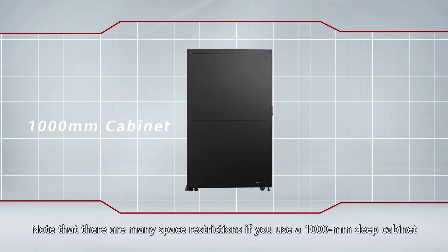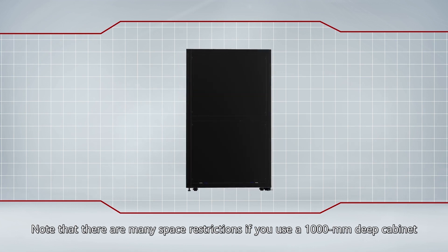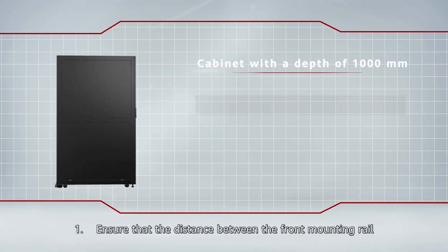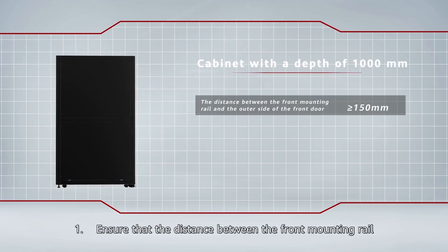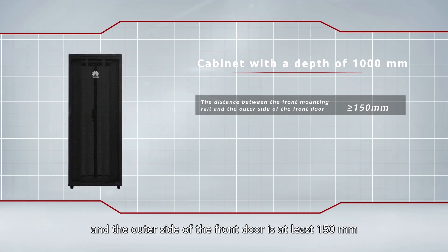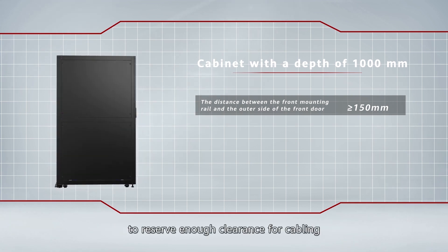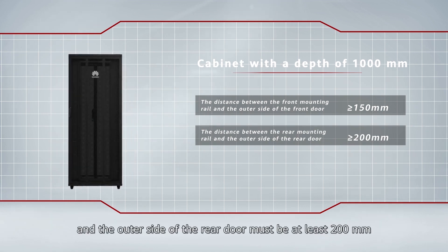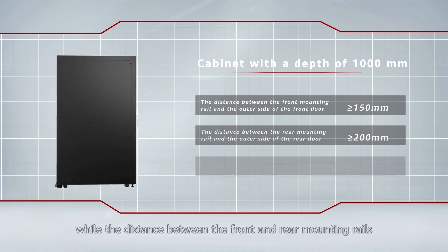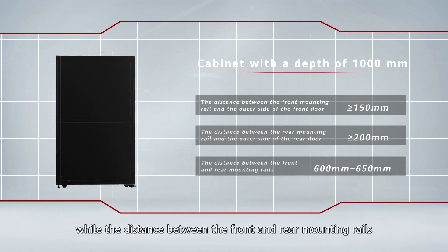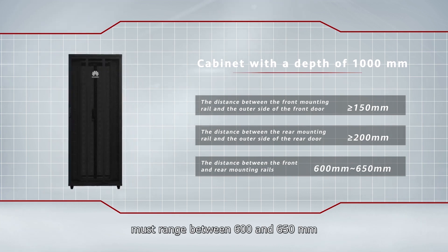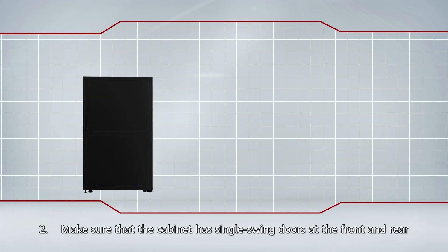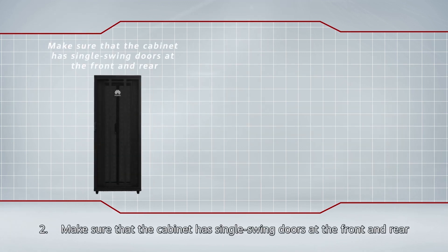Note that there are many space restrictions if you use a 1000-millimeter deep cabinet. You need to check three key issues during the site survey: ensure the distance between the front mounting rail and the outer side of the front door is at least 150 millimeters. The distance between the rear mounting rail and outer side of the rear door must be at least 200 millimeters, while the distance between the front and rear mounting rails must range between 600 and 650 millimeters to guarantee adequate cabling clearance for the PDU.